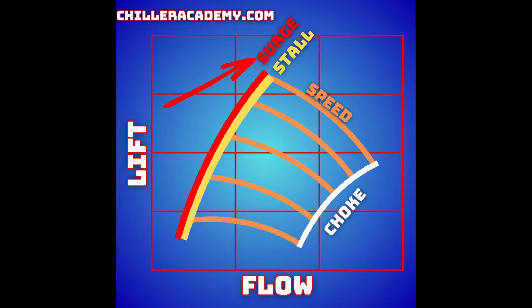Surge, just from a high level, let's be real clear on what we're describing here. Surge is when we exceed the impeller's ability to move refrigerant due to how much of a pressure difference there is across the impeller. What that results in is a reversal of flow through the impeller. The impeller still maintains RPM and its rotation, but the refrigerant from the discharge side literally reverses back into the suction, and they equalize momentarily, and then it's able to reestablish flow. When you have constant repetitive surges, we surge for a moment, it comes back out of surge after it equalizes some, then it starts to build pressure up again very quickly, and then surges again, and we get into this back and forth.